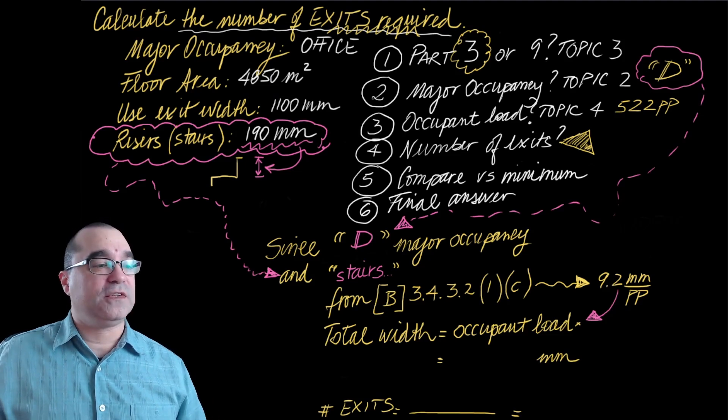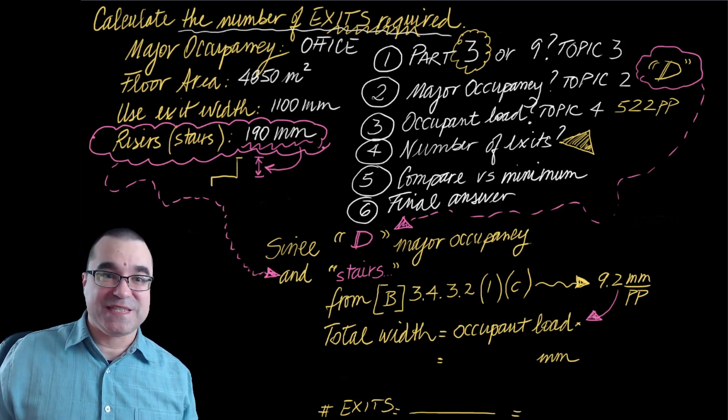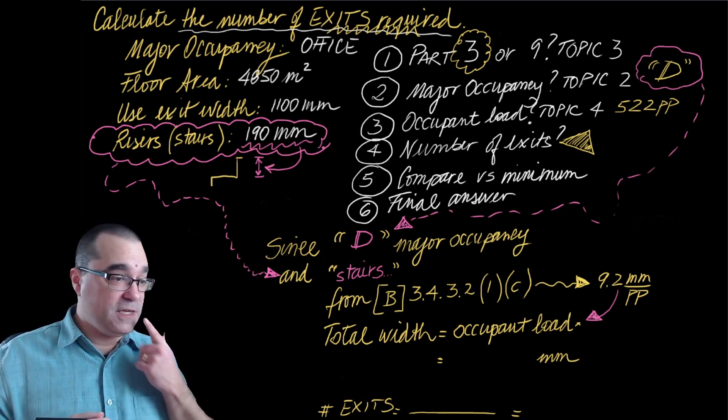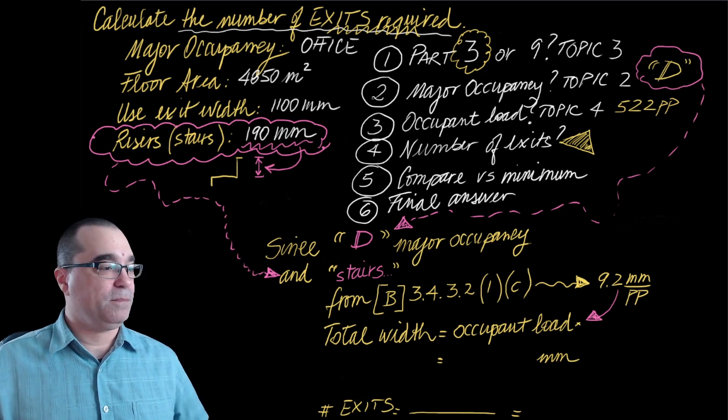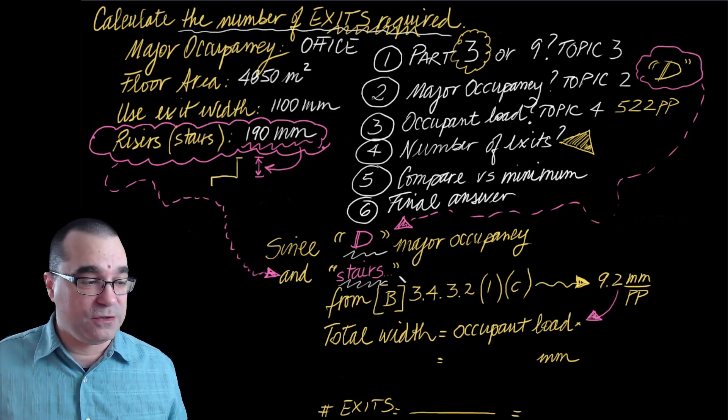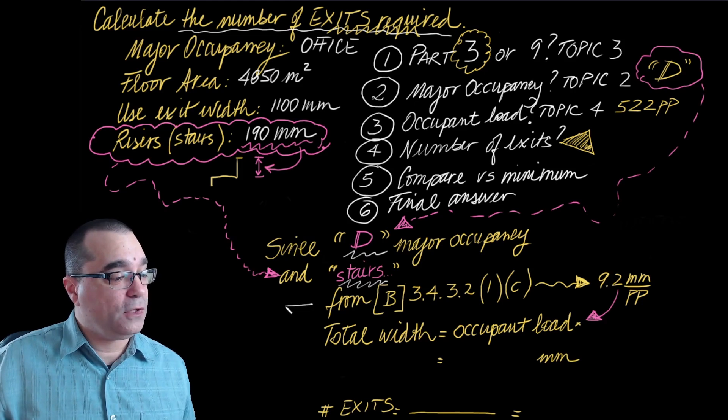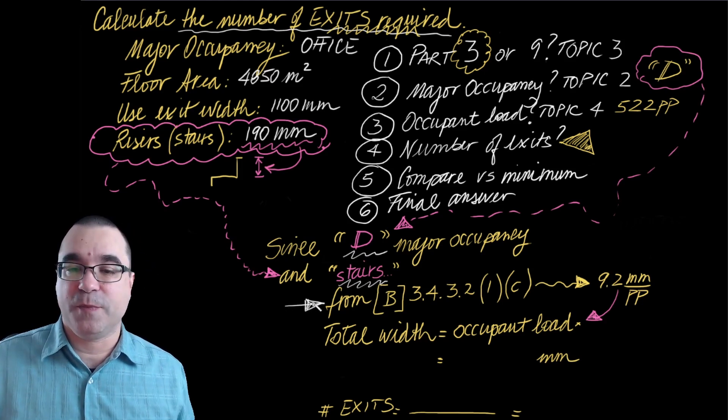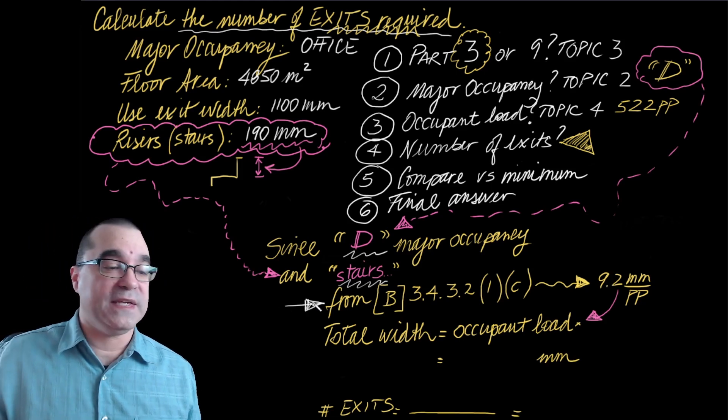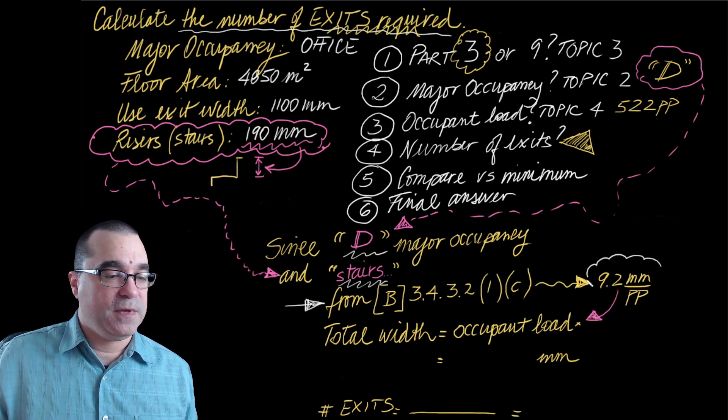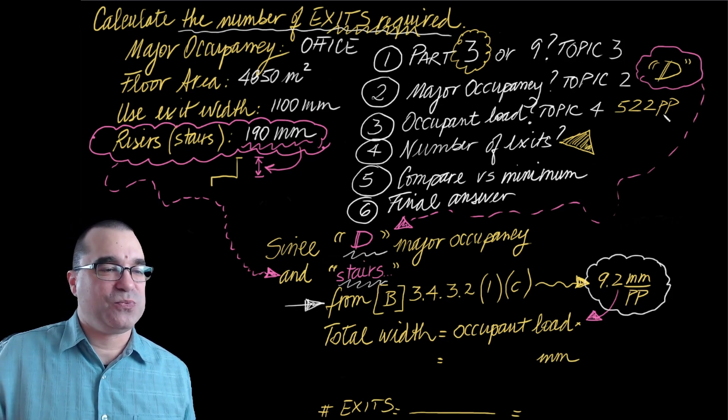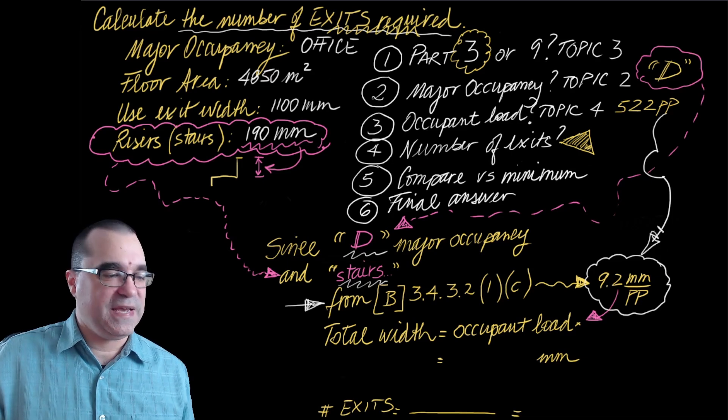For step number four, we have to determine what the number of exits is going to be based on the information we have here. Just based on the geometry and the occupant load, what we have here. So since this is a D major occupancy, and because we're looking at the width of stairs and the number of stairs, the appropriate location in the Ontario Building Code where to get this information is under clause 3.4.3.2(1)(c), which says that the minimum width for each person is going to be 9.2 millimeters. So that's where the occupant load comes into play.